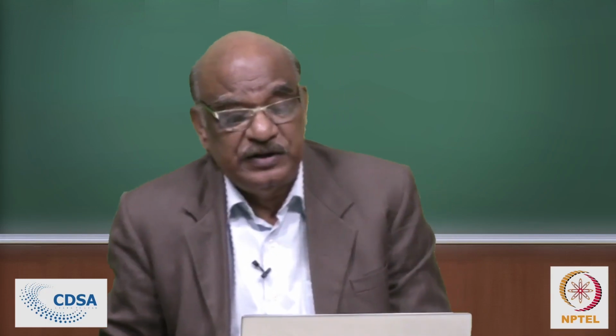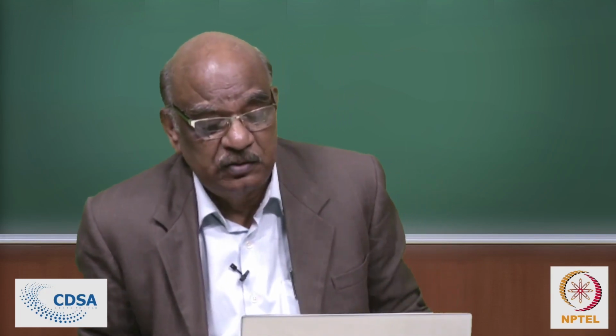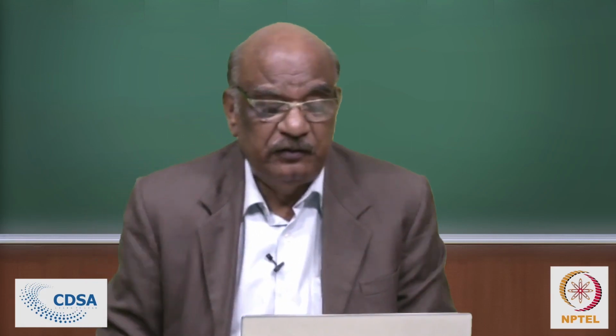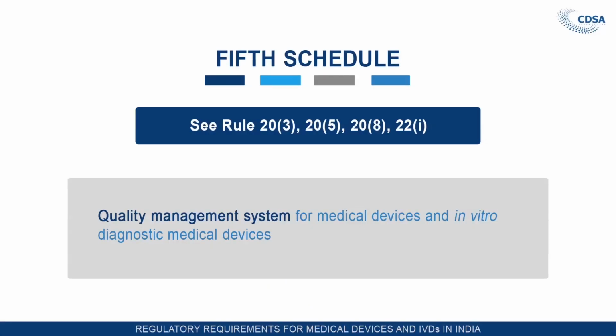QMS is an addition to the drug and cosmetics rules with the introduction of the medical devices as a controlled item. QMS was not there earlier, but now it has been introduced. Fifth schedule, Rule 20(3), 20(5), 20(8) and 22(i). Quality management system for medical devices and in vitro diagnostic devices. This is in the medical device regulations, fifth schedule.